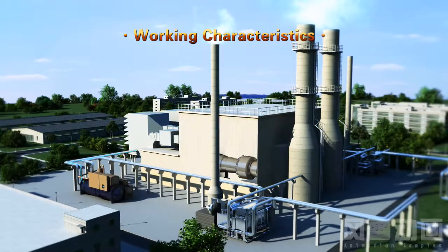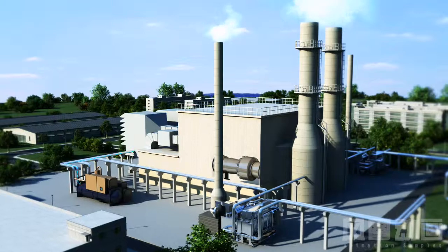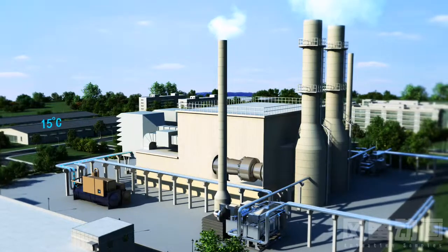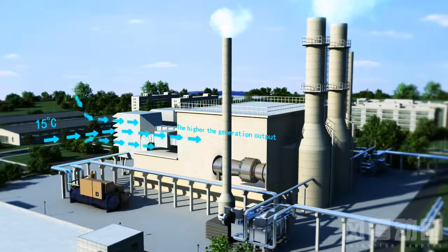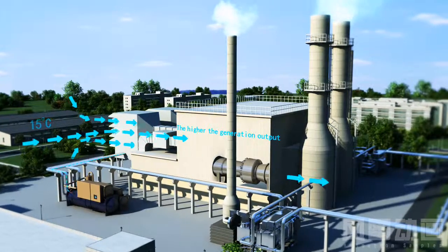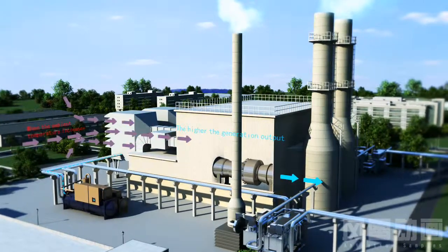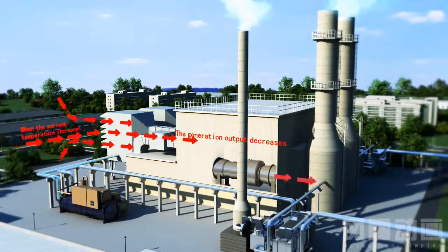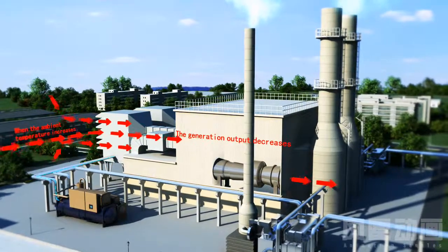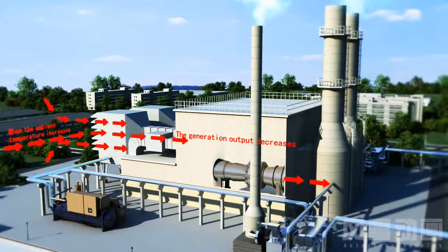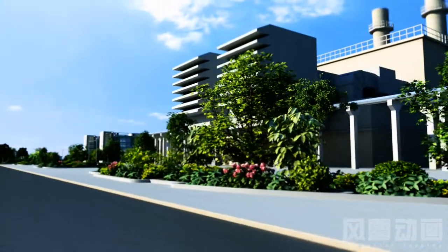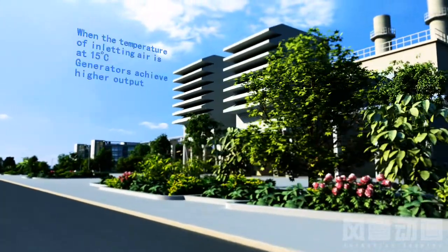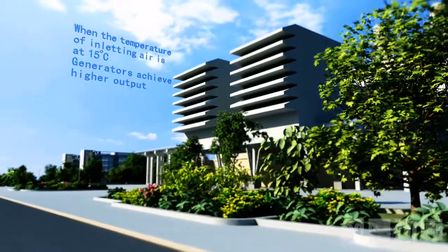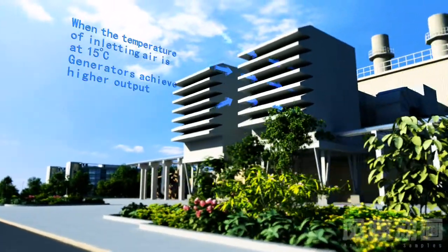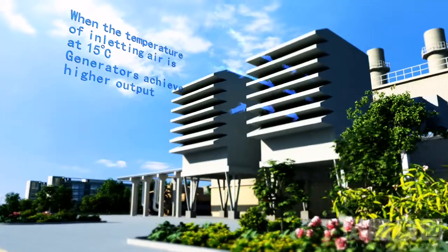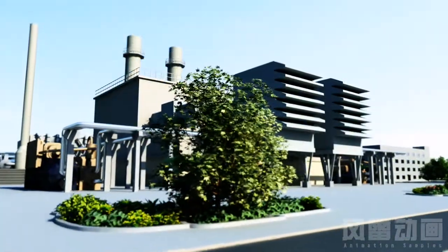Working characteristics of the gas turbine. The air inlet temperature has a great impact on the generation efficiency. Namely, the lower the inlet temperature is, the larger the inlet mass flow is, and the higher the generation output is. Contrarily, the generation output decreases as the environment temperature increases. Therefore, the designed work condition of the gas turbine power generation is 15 degrees centigrade for the air inlet temperature, under which the generators achieve higher output.